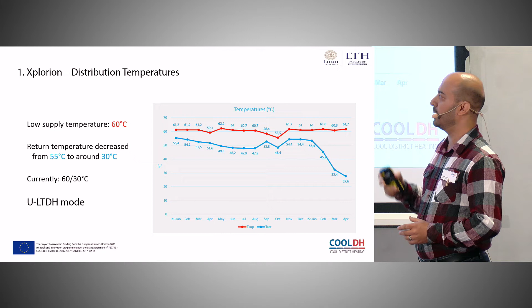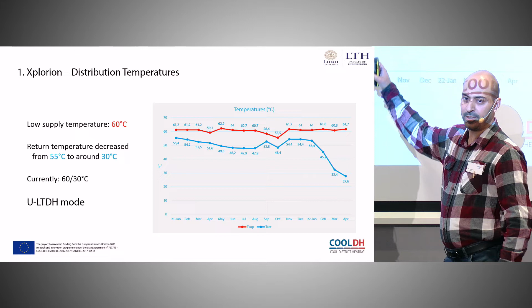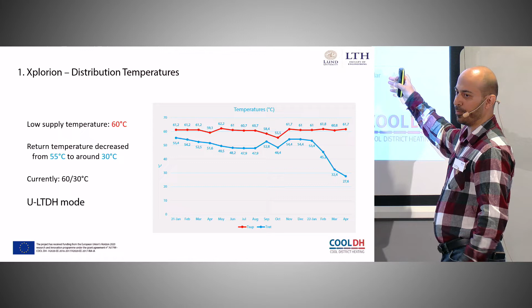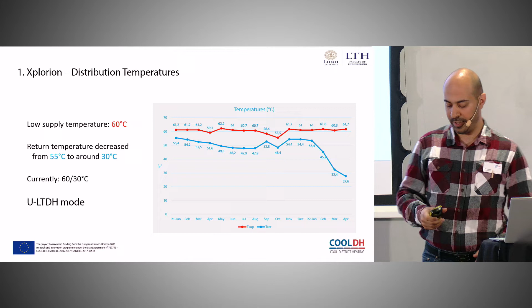So currently the system is working with the heat pump in ultra-low temperature mode, with a supply temperature of 60 and a return temperature of near 30. And I should mention that during this time period, the heat pump was in operation for just 2 months. It ran for 1 month last September, and after that, because of the high return temperature, the operation was stopped. Again, by fixing the problem, the heat pump started to operate by the end of March, and in April it was in normal operation.